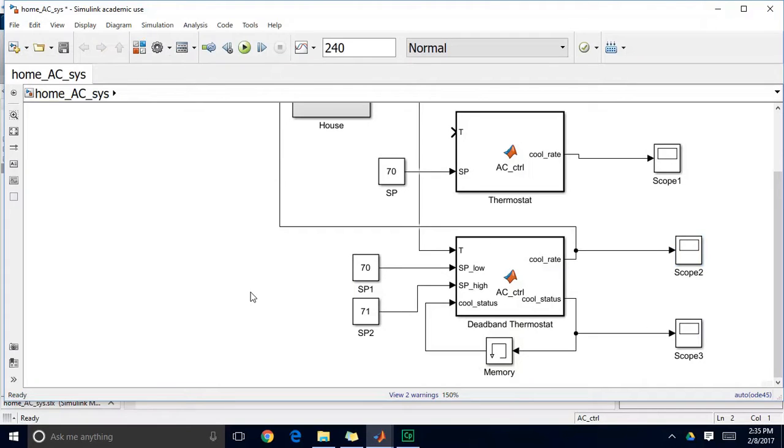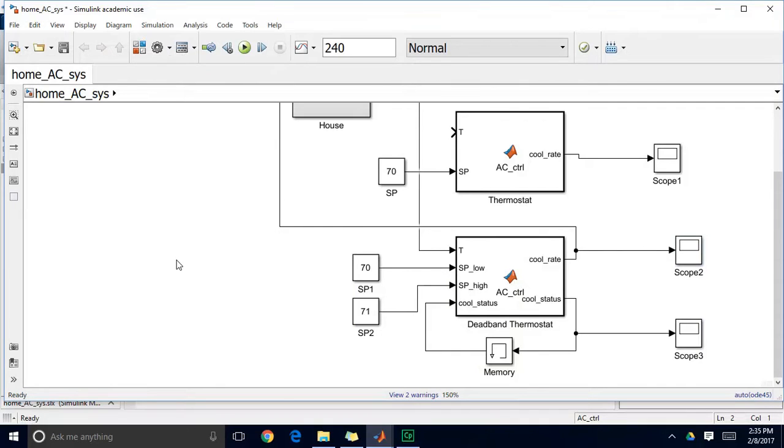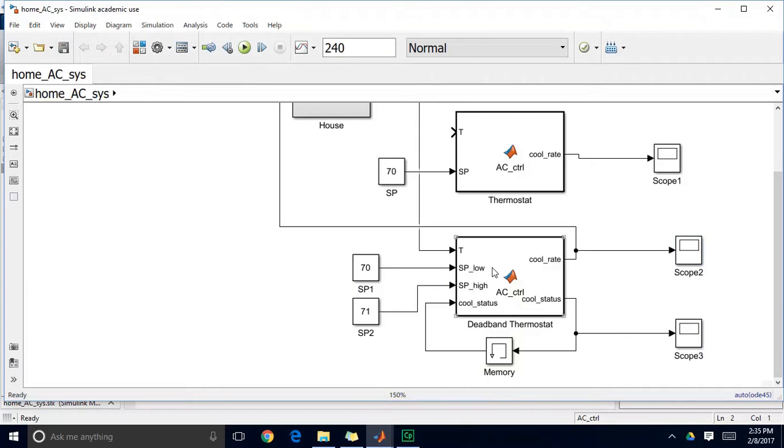So this is a way to have hysteresis in your system, which is a desirable behavior for an on-off controller so that you don't get frequent switching because your temperature is crossing its setpoint very frequently. So I've shown you this because this memory block and doing logic like this gives you a lot of freedom to customize logic in your system.